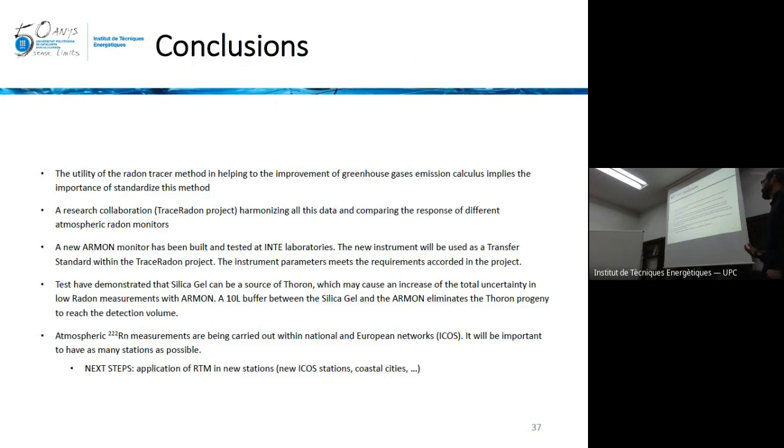of standardizing this methodology. The research collaboration, which is the TraceRadon project, is analyzing all this data and comparing the response of different atmospheric radon monitors. A new monitor for radon concentration has been built and tested at PTB laboratories, and this instrument will be used as transfer standard for the project.